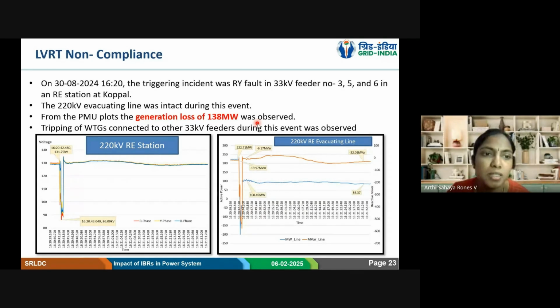So here what happened was on 30th August, there was some RY fault in 33 kV feeders of the RE station. For that fault, the 220 kV line was intact, but the RE, the IBRs got tripped. The WTGs connected at 33 kV got tripped. So it is the non-compliance of LVRT protection.